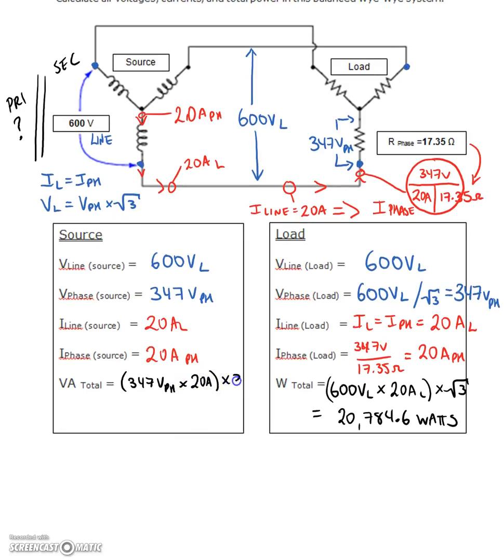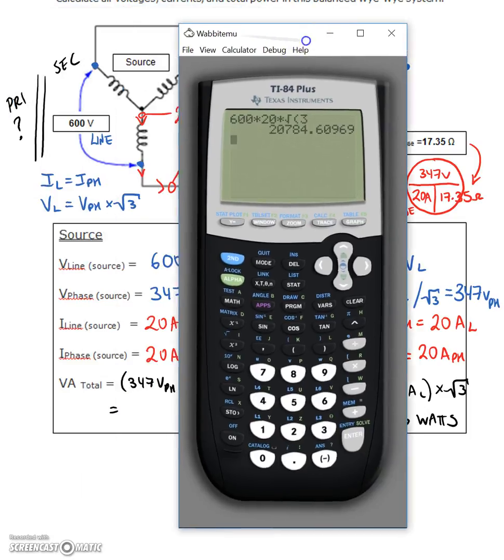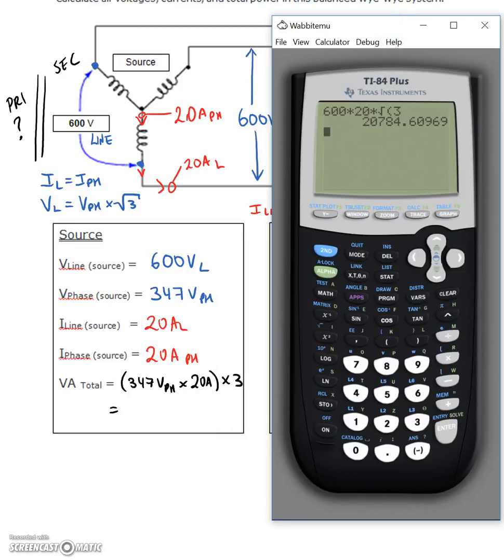347 volts on the phase times 20 amps on the phase. And we're multiplying that by three. So again, we've got 347 volts on the phase, we have 20 amps on the phase, and we're multiplying those guys by three. 20,820.